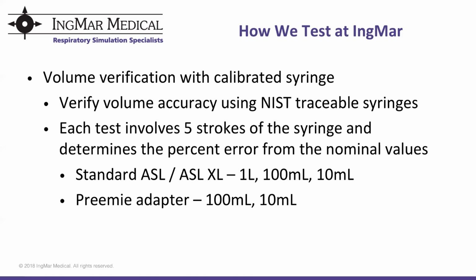The next test we perform is called volume verification with a calibrated syringe. For the volume verification, we use 3 NIST traceable syringes. Our testing consists of setting up a passive patient model and providing 5 strokes from each syringe to verify the volume accuracy of the lung. As you can see on the slide, we use 3 syringes for the standard ASL and the larger ASL XL. And when a preemie adapter is used, we use 2 syringes.